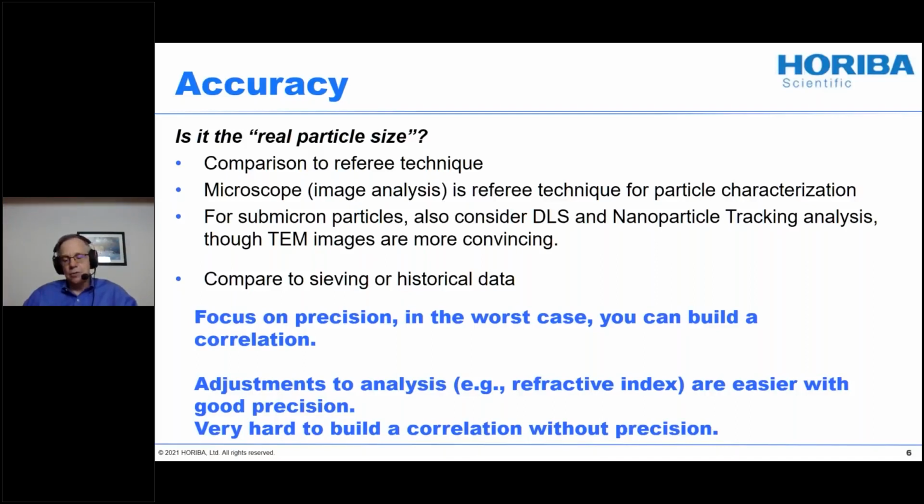And your question will then become, is the number from laser diffraction close enough to the number you need to move on with your life? If you look at FDA guidance, you'll see discussion of comparison to a referee technique, which is most often image analysis or microscopy. And that makes a whole lot of sense. And we do suggest that you use multiple techniques, particularly as you're setting up methods, to confirm that everything is in the right neighborhood.